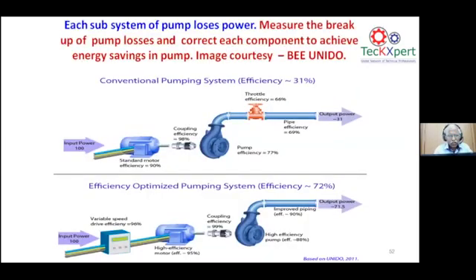Leave alone the pressure in the pumping system. In the pumping system, one loss is happening in the pump, the other loss is happening in the piping. Almost you can see the piping efficiency is only 70% and the pumping system efficiency is 30%. If the pumping system efficiency is increased to 70%, definitely with improved piping it goes from 70% to 90%. Piping is an area which Indian agriculture has understood, but industry has definitely not understood. We have to go for GI pipe or MS ERW pipe, especially on the water line pumping, and go for rigid PVC piping.